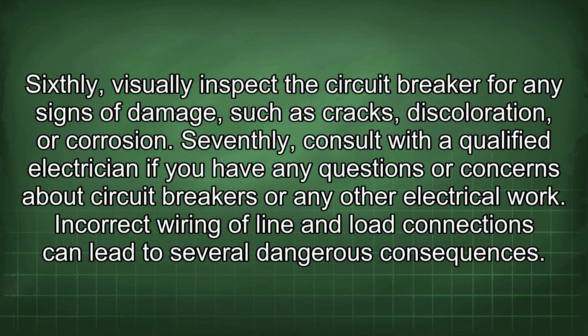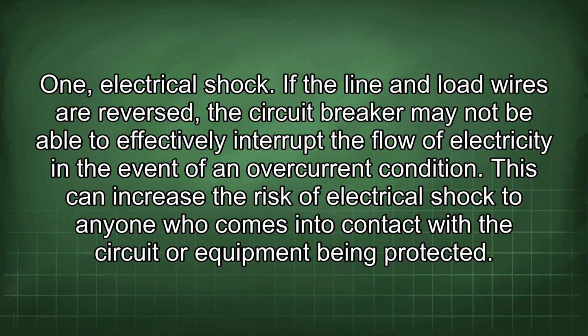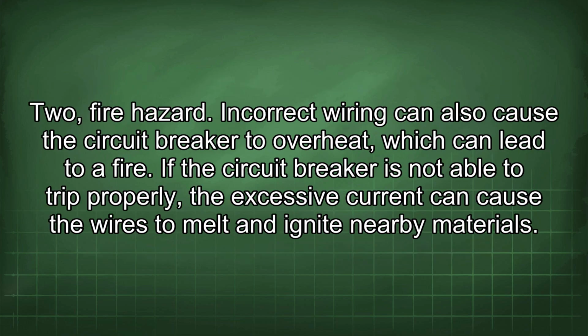Incorrect wiring of line and load connections can lead to several dangerous consequences. 1. Electrical shock. If the line and load wires are reversed, the circuit breaker may not be able to effectively interrupt the flow of electricity in the event of an overcurrent condition. This can increase the risk of electrical shock to anyone who comes into contact with the circuit or equipment being protected. 2. Fire hazard. Incorrect wiring can also cause the circuit breaker to overheat, which can lead to a fire.